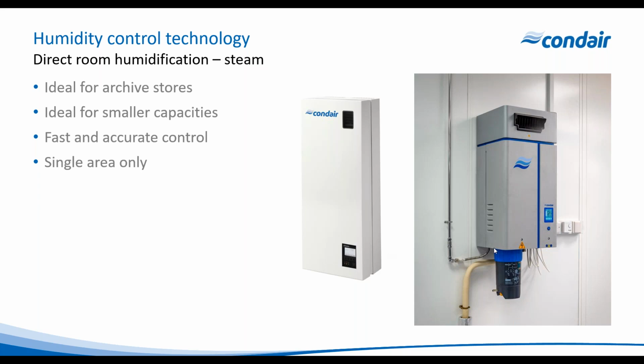Slightly bigger systems, you can use a standard resistive heater, as in the image on the right, with a fan box on the top to blow steam into the space. Again, you wouldn't put a system like this in a public area because we've got hot drain pipework, we've got hot surfaces, we've got steam coming out of it, and we've got a control panel that can be interfered with. So we definitely wouldn't want to put those in a public area, but for archive stores, it's very common to see these types of units. And you'll get fast and accurate control, but just for a single area.